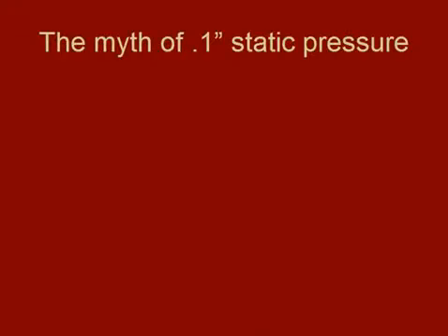We're going to talk about a lot today, and the most important thing, the thing that I would like to think I spent my adult life defeating, is this myth of 0.1 static pressure, that you can go to a duct calculator, pick it up, and just put whatever volume of air you want opposite 0.1, and that automatically gives you the duct size. I wish life were that easy. It's not. Nothing is. My dad used to say, if you make a system so easy that even a fool could use it, then only a fool would use it. Trust me, this applies here.